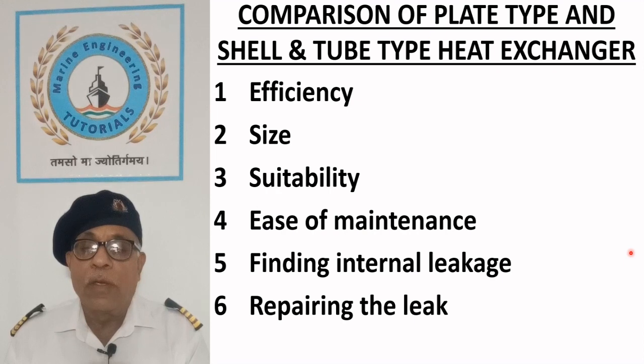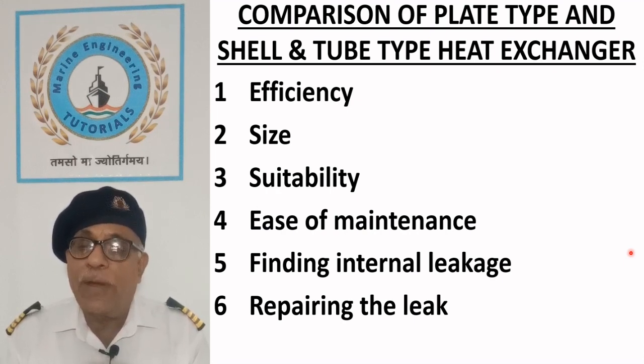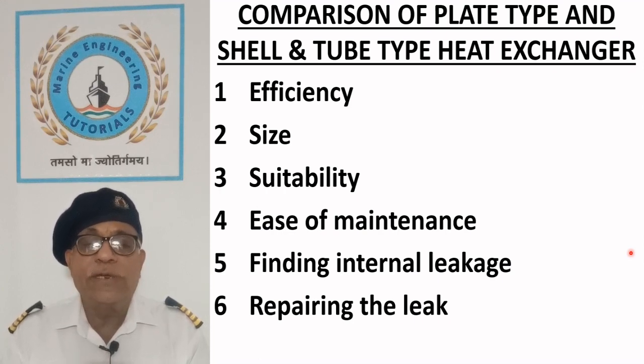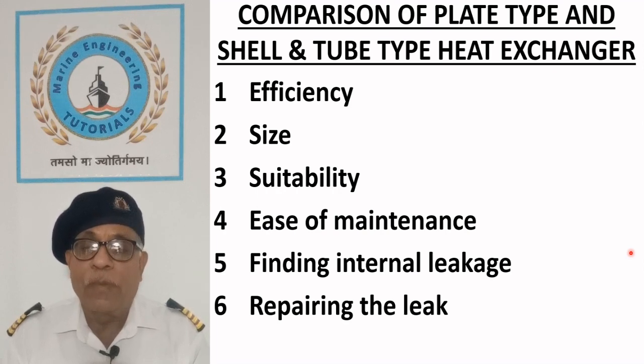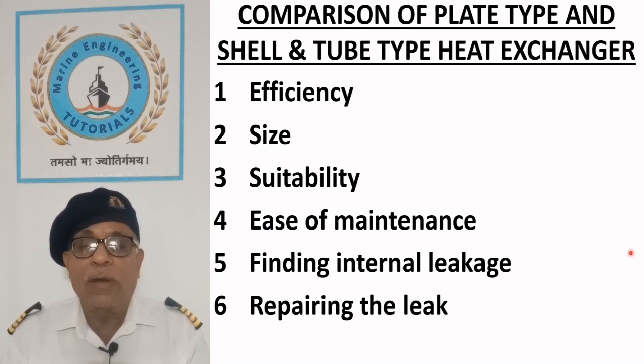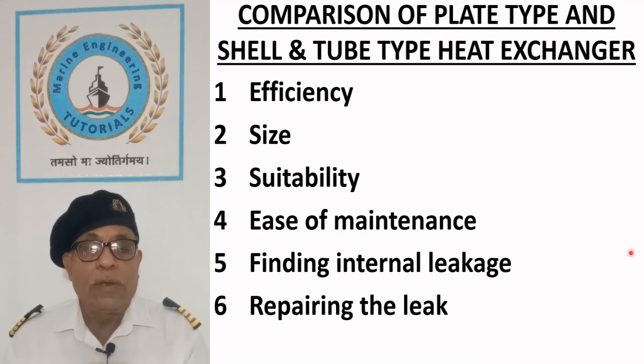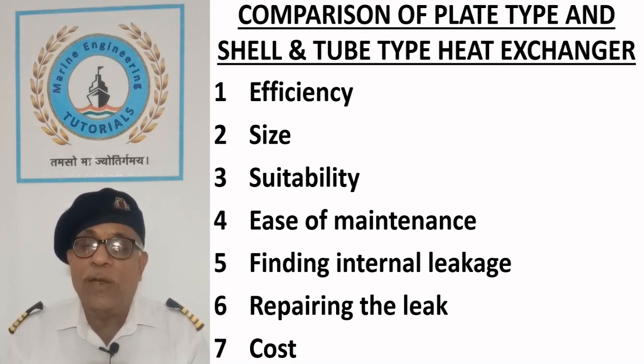Repairing the leak. A plate type heat exchanger can be quickly repaired either by removing the defective gasket or exchanging a set of defective plates with spare ones. Whereas shell and tube type heat exchanger require plugging of the tube. If spare plates or gaskets are not available, heat exchanger can still be operated by removing the defective plates set with reduced plate stack length and reduced capacity. Cost. Plate type heat exchangers are expensive as compared to shell and tube type due to use of titanium plates. Advantages such as compact size, ease of cleaning and better efficiency outweigh their initial higher cost.